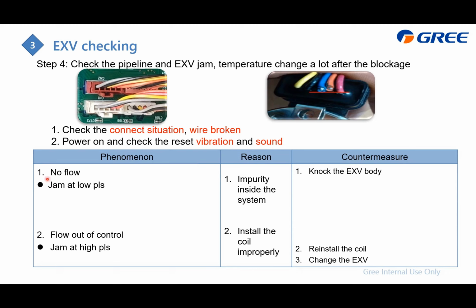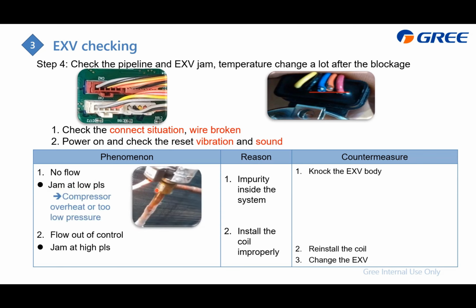And the first is no flow. That means the inside pin of the EXV is stuck or jammed at the low pulse. And here is the detail. You can also find that the outlet of this EXV becomes lots of ice, it becomes frozen. And also at this time, there's not enough refrigerant to flow back to the compressor. At that time, the compressor discharge temperature will also be very high.